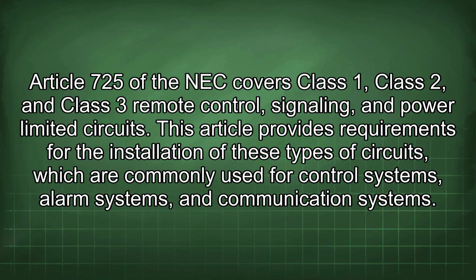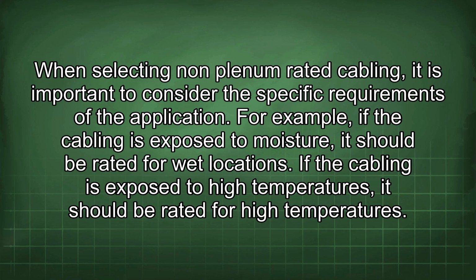Article 725 of the NEC covers Class 1, Class 2, and Class 3 remote control, signaling, and power-limited circuits. This article provides requirements for the installation of these types of circuits, which are commonly used for control systems, alarm systems, and communication systems. When selecting non-plenum rated cabling, it is important to consider the specific requirements of the application.